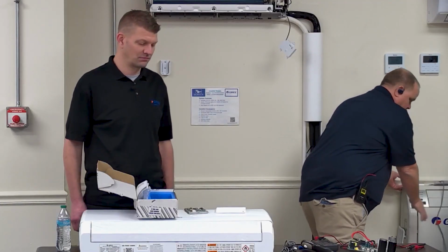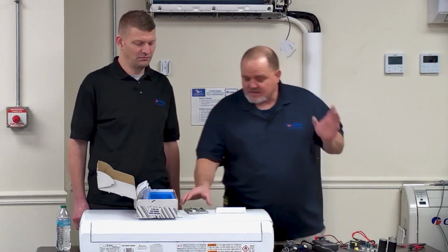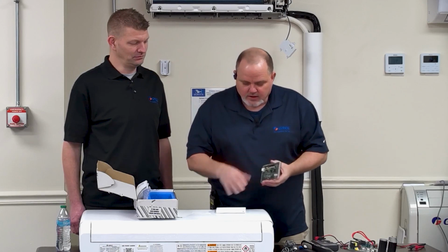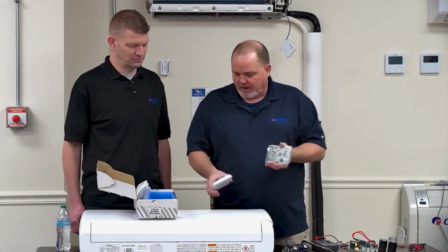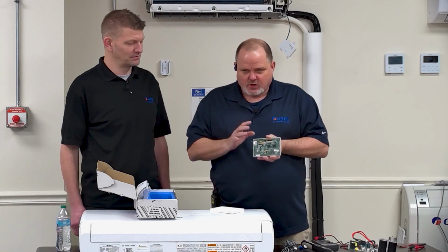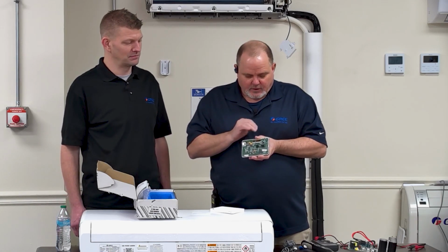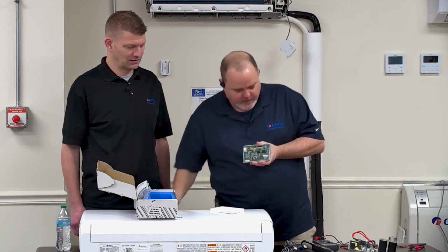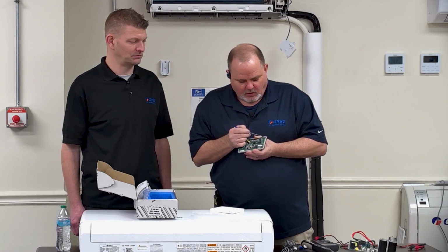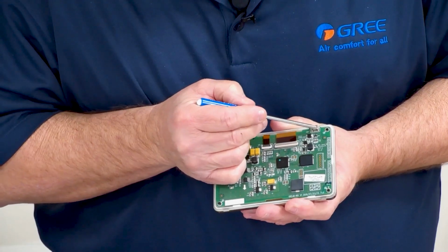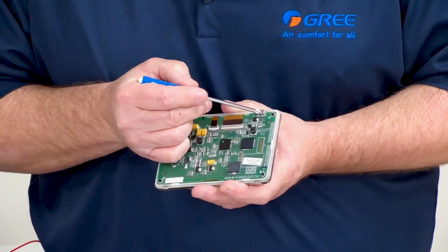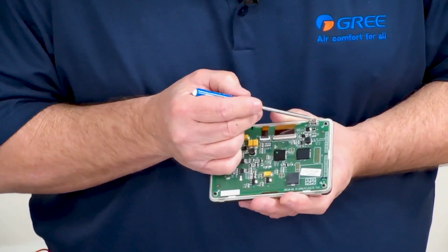Now, the reason I have this taken apart is because it's really easy to pop apart. I just used like a pocket screwdriver. I popped the thing apart. It's a great service tool. The one thing that GREE didn't do a very good job of is right here. This is that USB power supply coming into it. The only thing that is wrong here is the only thing that's holding that in there is the 4 solder joints for the 4 wires. So it breaks really easy.